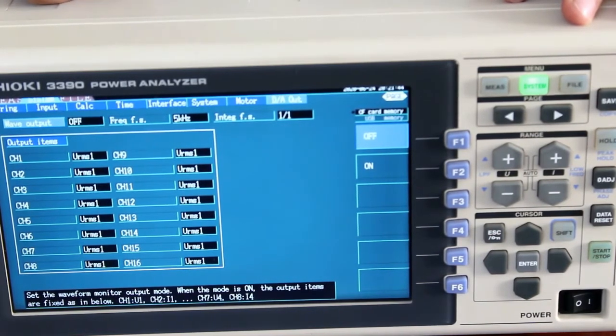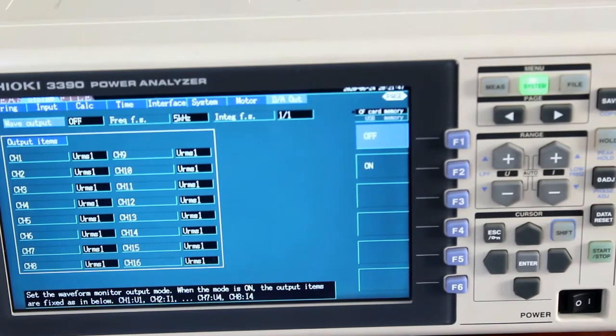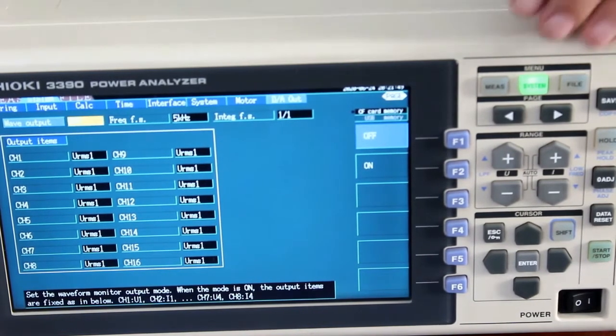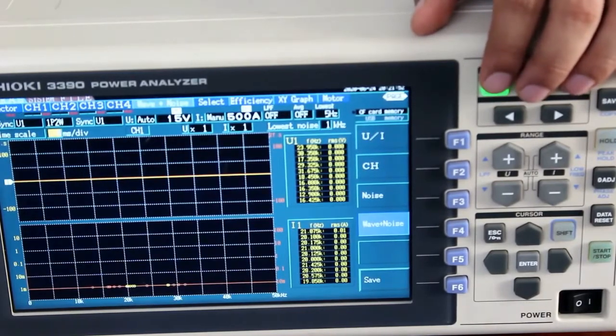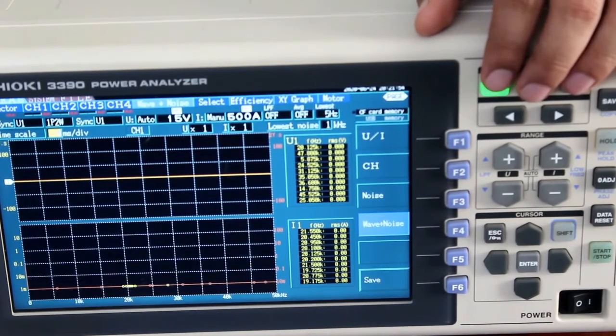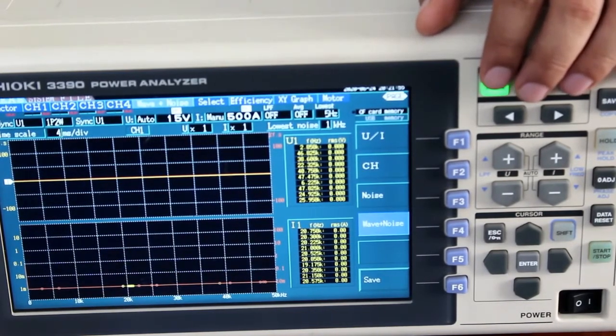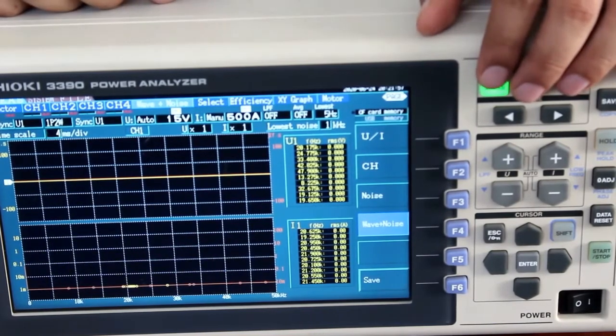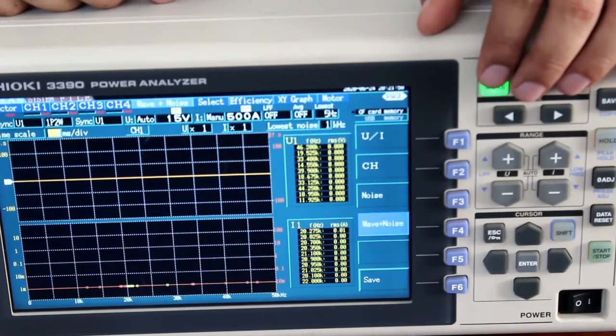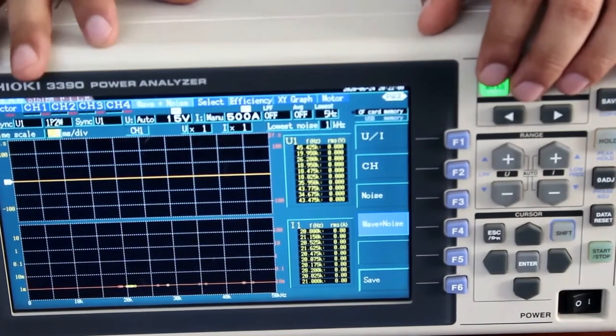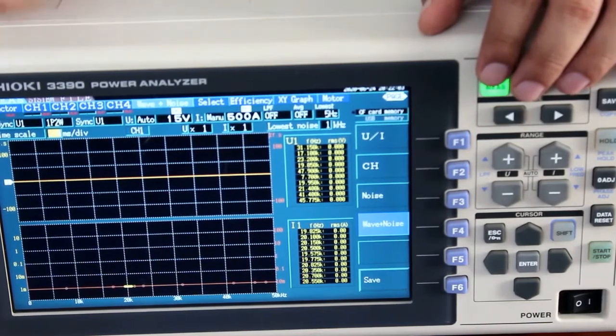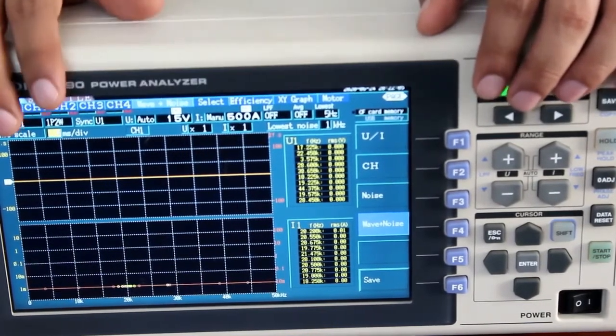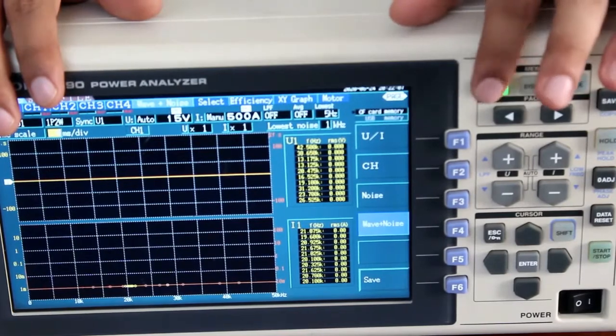The DA output setting allows you to take parameters out in the form of analog signals and feed them into a secondary data logger to log parameters. Now I'll go to the measurement screen, where you can see all types of parameters: waveform, noise calculation, harmonics, and vectors.